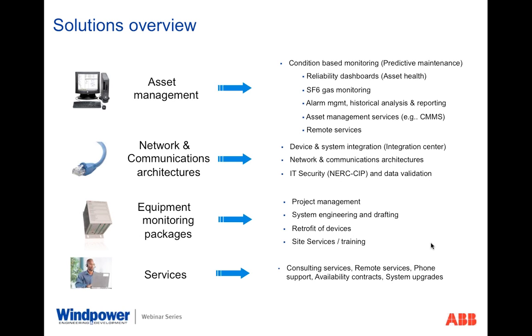As we discussed in the previous slide, getting the information to the right person is critical to any successful monitoring solution. Implementing intelligence at the asset level will increase productivity for the end user, with features like alarm management, reporting, and even alarm notification for critical issues that arise. As for equipment monitoring packages, they are installed at the asset level, or in this case, the breaker control cabinet in the substation.